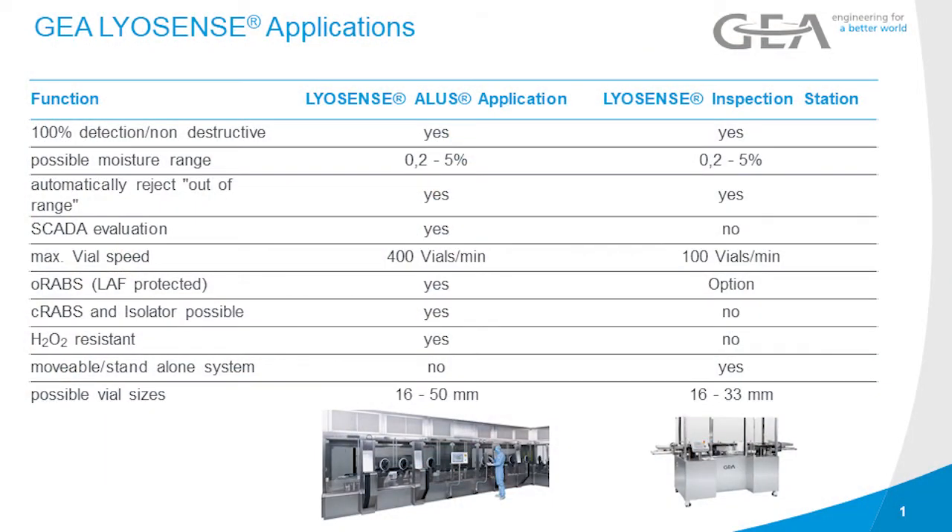The standalone station has the same functionality as the ALUS version but comes without the SCADA evaluation. The station was designed for manual loading and unloading. Process parameters like vial speed can be set using an integrated touchscreen, and more advanced options like the definition of residual moisture limits can be controlled via an attached laptop computer.